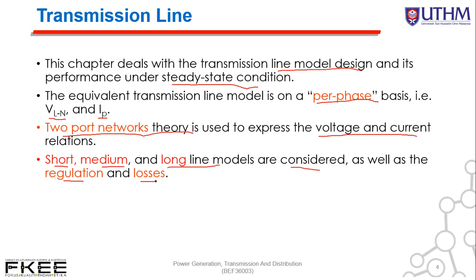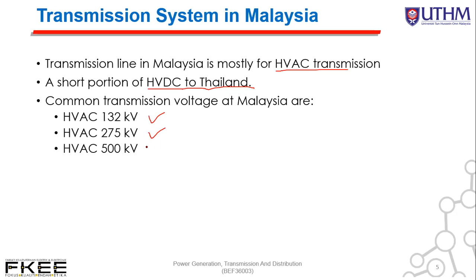So if we look at transmission system in Malaysia, basically we have transmission line in Malaysia is mostly for high voltage AC transmission, and there is a short portion of high voltage DC, direct current, that is from Gurun, Kedah to Thailand, which is about 110 kilometer long, supply about 300 kilovolt overhead line. And the common transmission voltage in Malaysia are 132 kV HVAC, 275 kV, and 500 kV HVAC.